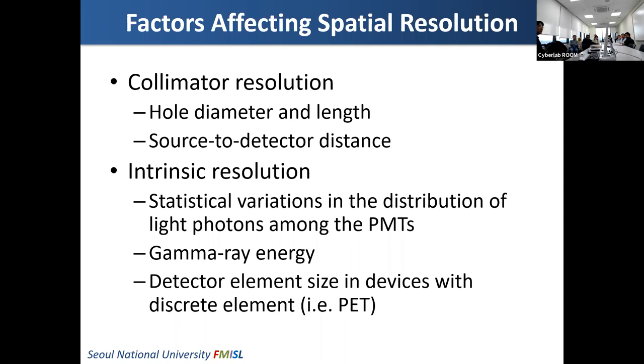How about intrinsic resolution? One of the main factors is the statistical variation in the distribution of light photons among the photomultiplier tubes. We use multiple photomultiplier tubes, but the gain of photomultiplier tubes are different, and the coupling between the photomultiplier tube and scintillation crystals is also different. The scintillation crystal itself is not homogeneous, so there is some random statistical variation in the distribution of light photons among the photomultiplier tubes.